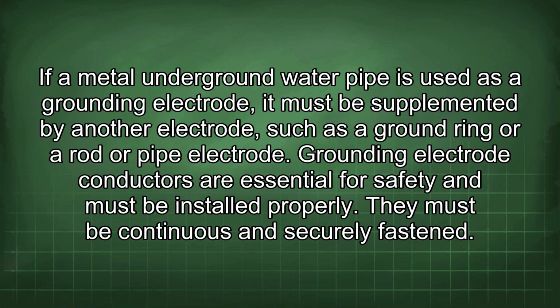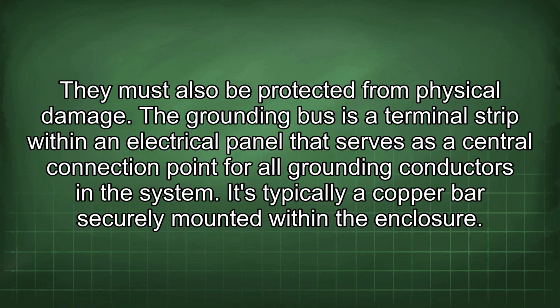If a metal underground water pipe is used as a grounding electrode, it must be supplemented by another electrode, such as a ground ring or a rod or pipe electrode. Grounding electrode conductors are essential for safety and must be installed properly. They must be continuous and securely fastened. They must also be protected from physical damage.